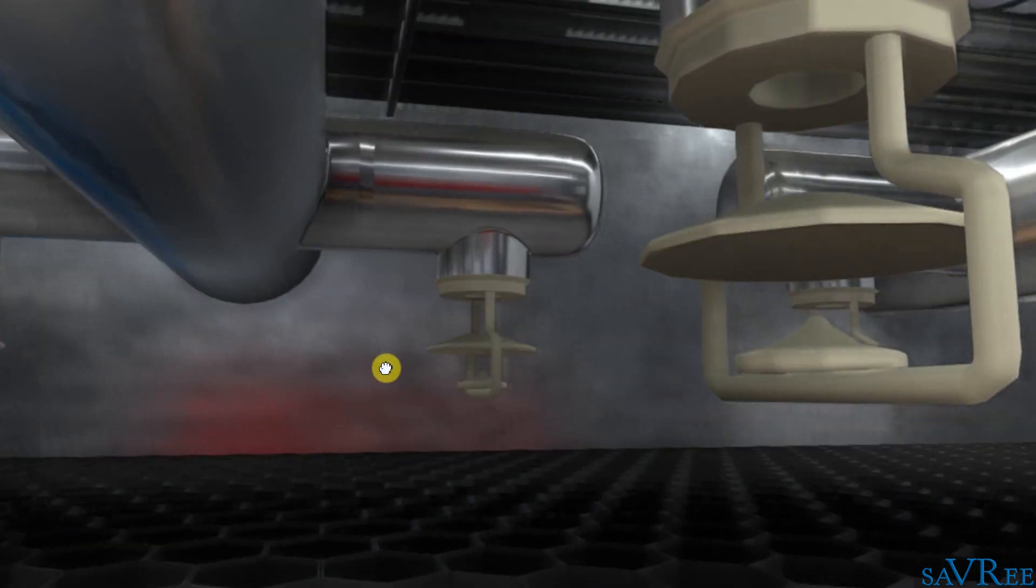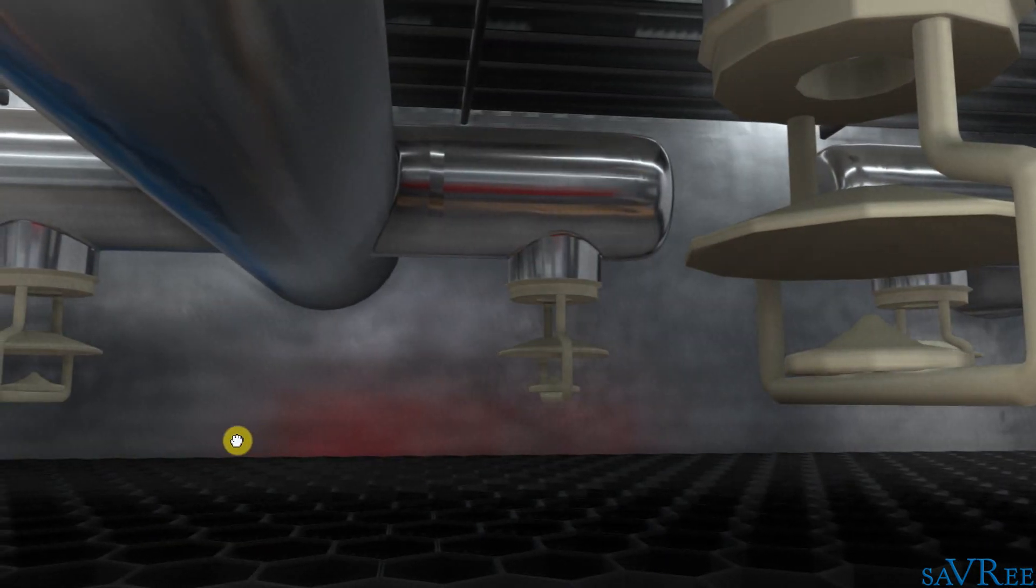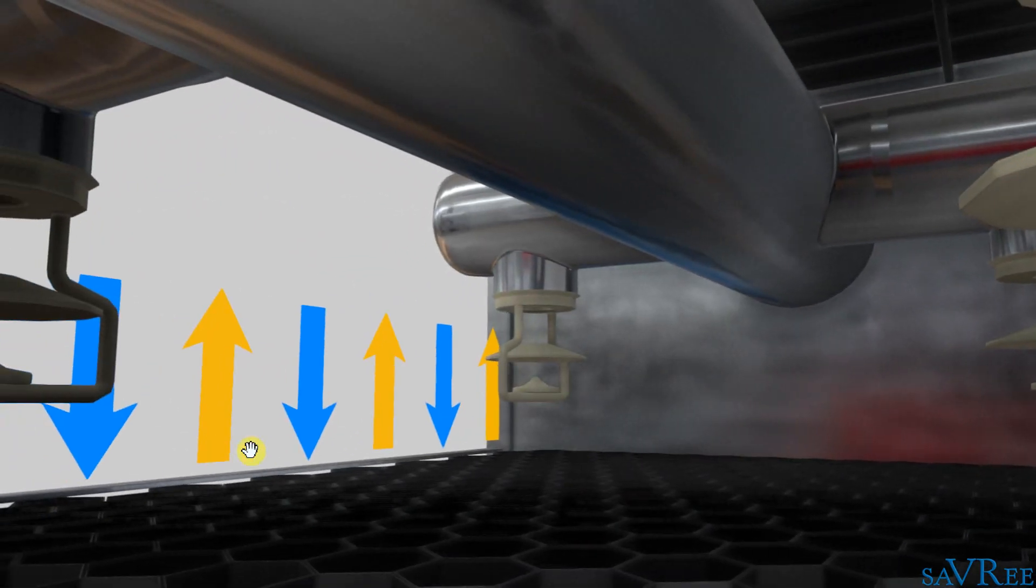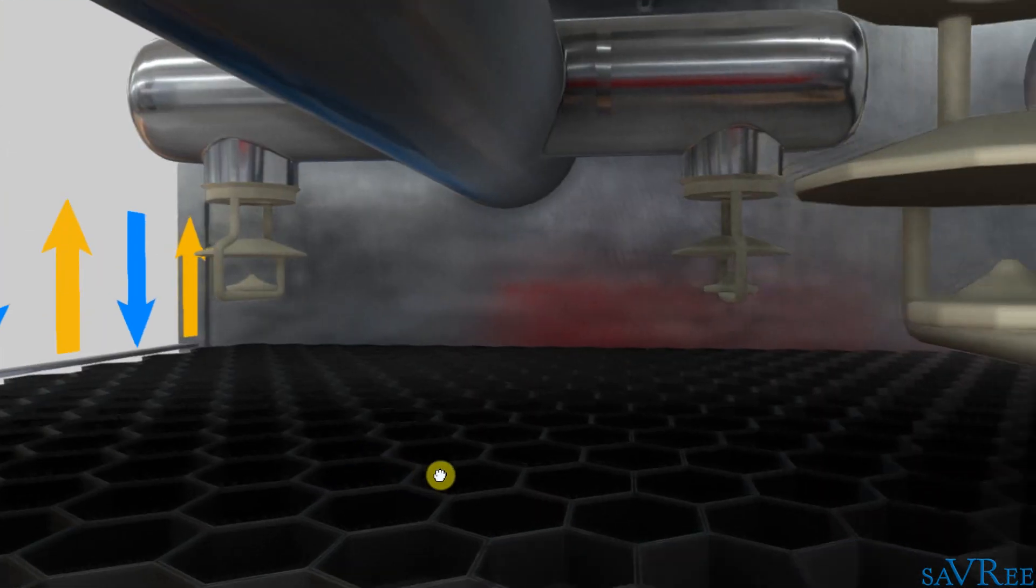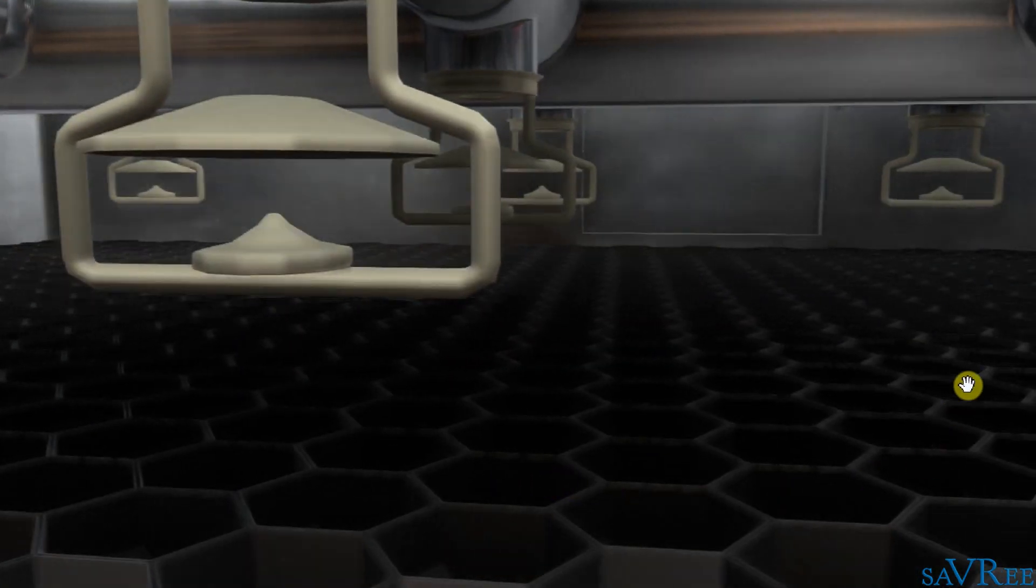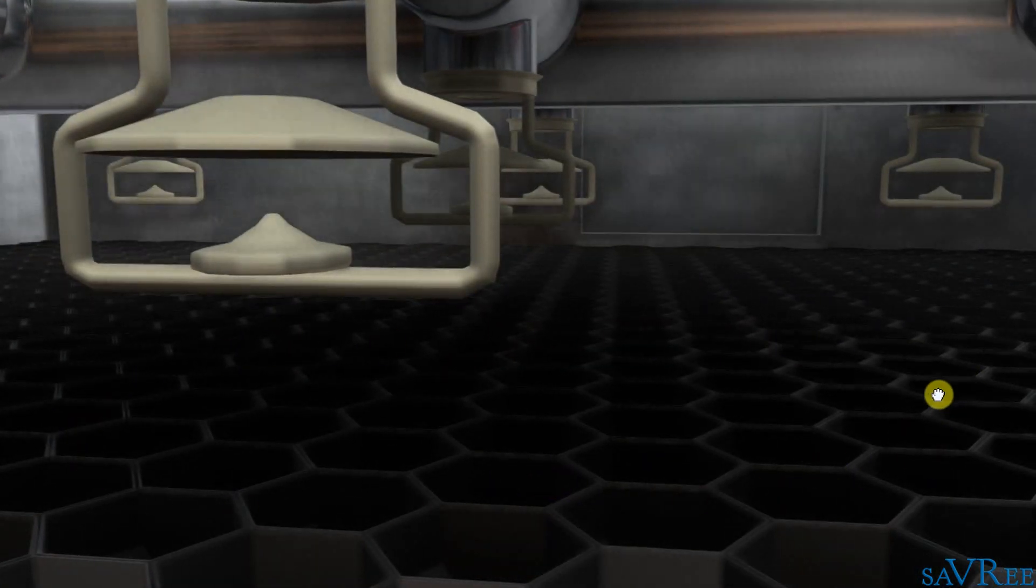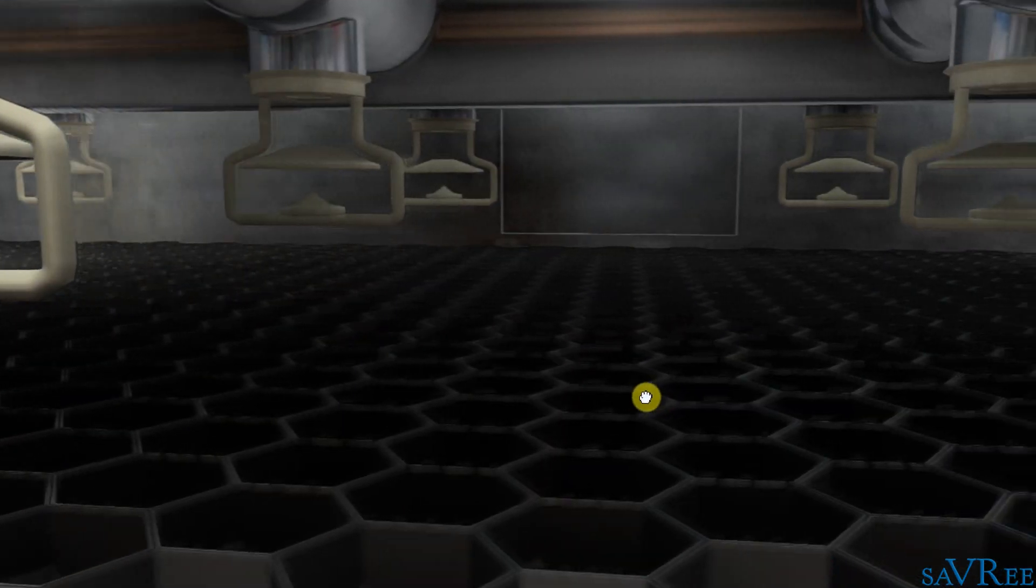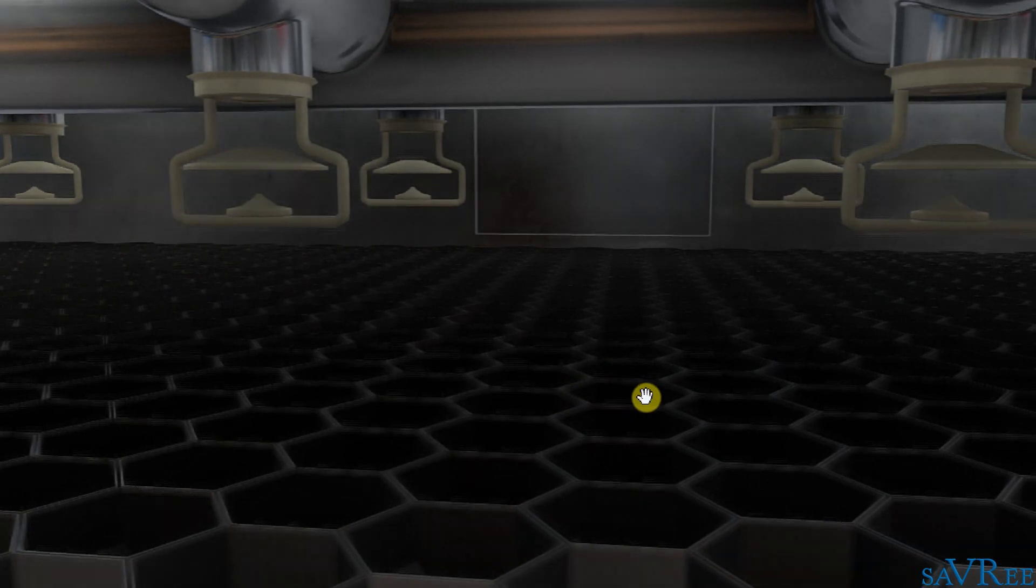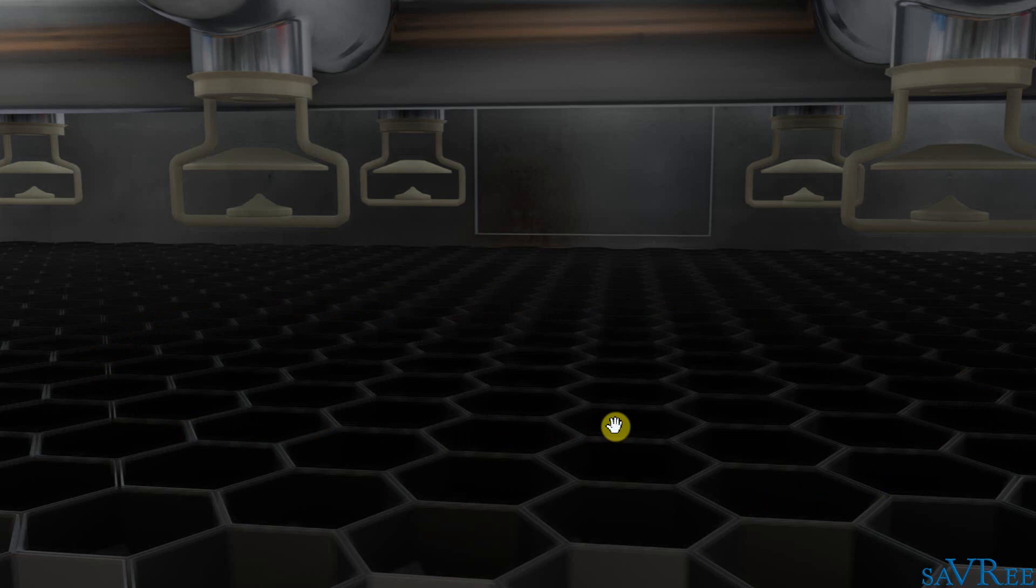We can see that we have multiple nozzles because we have quite a large area to cover. We need to spray all of this black area here, so we need to cover as much of the fill as possible. This fill is actually called film fill. There's two types that you're likely to see: one is film fill and one is splash fill. Splash fill is used more for cross flow type towers, so we're not going to talk about that too much in this video because this video is about a counter flow type cooling tower.